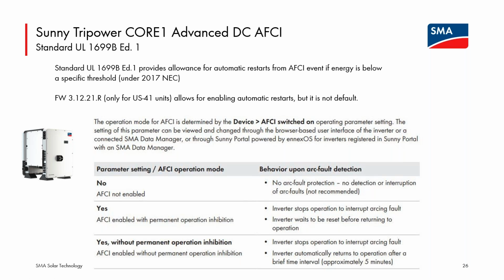A lot of feedback we've gotten from customers: we have been including arc fault detection in our inverters for many years now, I think 11 years. We have improved our algorithms quite a bit. Anyone listening who deals with our inverters, if you see continuous arc errors on the inverter, please treat those as real. It may be very hard to visually identify where in the array the arc is occurring, but if you are seeing multiple issues with an inverter, please treat them as real.